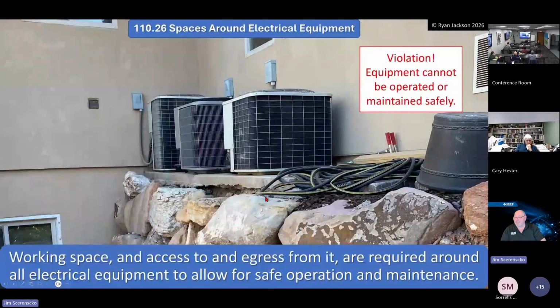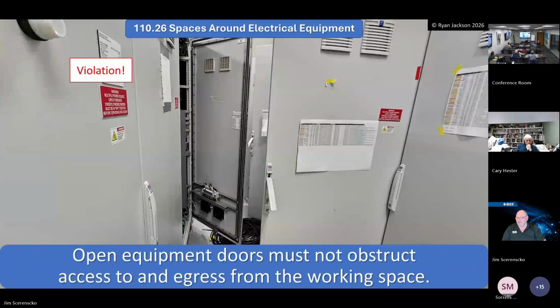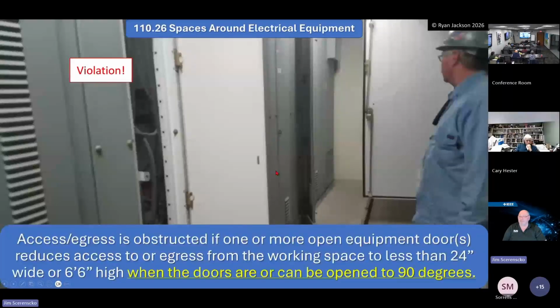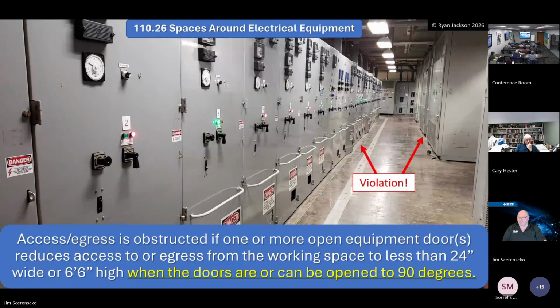And then spaces about equipment: working space and access to and egress from are required. Open equipment doors must not obstruct the egress out. If the doors open and obstruct, it is a violation. We had this happen in Portland also. A big piece of switchgear, and it opened up to give you no space to get out of that workspace. You have to provide exit out of the workspace, not just out of the room. If you open those doors, you would limit the workspace. You would not have what you needed to get out of that workspace.